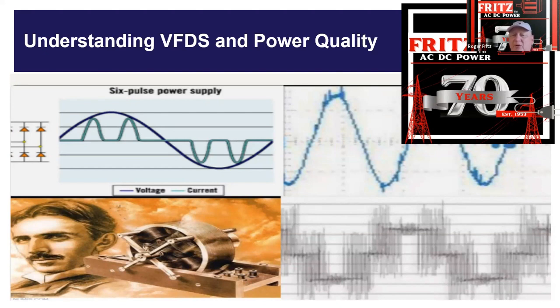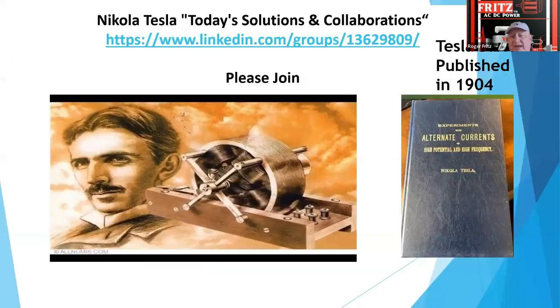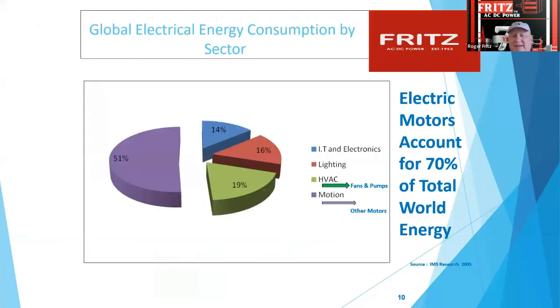And the code is to keep this below about a 2% voltage distortion. But you can see the output, this is actually a scope reading of the voltage output. And so you can see this has a multitude of pulses that are regulated, and they actually take up to about 12,000 pulses per wave. So with electronics, they've evolved a long ways, and they can do switching very fast.